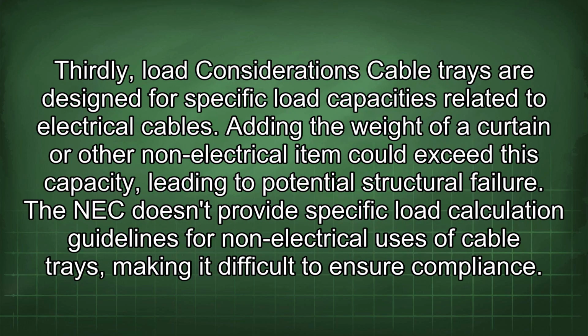Thirdly, load considerations. Cable trays are designed for specific load capacities related to electrical cables. Adding the weight of a curtain or other non-electrical item could exceed this capacity, leading to potential structural failure. The NEC doesn't provide specific load calculation guidelines for non-electrical uses of cable trays, making it difficult to ensure compliance.